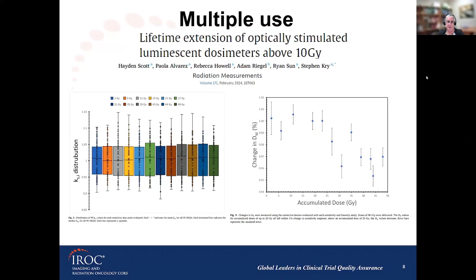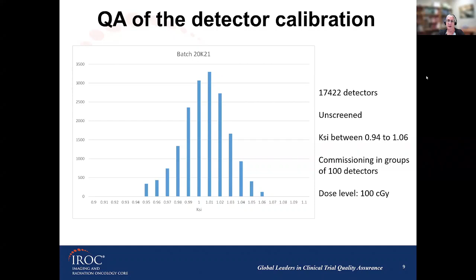So let me show what type of QA we are doing in IROC. We already went through more than 6 batches of OSLDs. And what I'm showing here is the distribution of KSI for our last batch, which is labeled 20K21. This batch has more than 17,000 detectors calibrated. Our detectors are under the condition of unscreened detectors. The KSI accepted values are from 0.94 to 1.06. The commissioning is done in groups of 100 at the level of 100 centigray dose level.